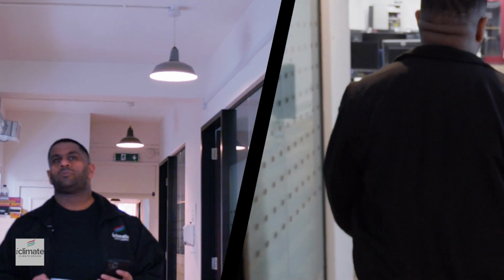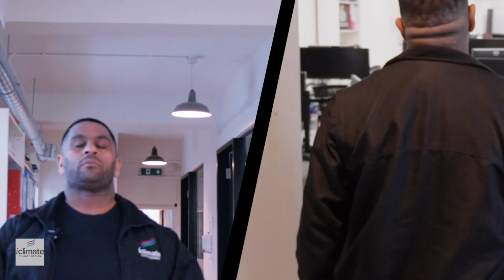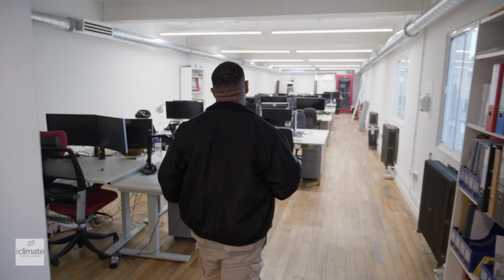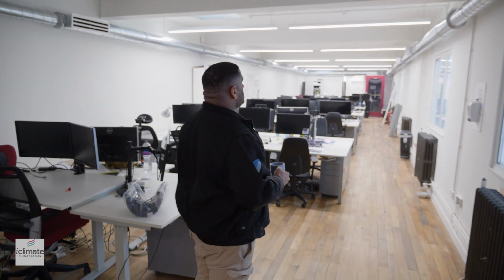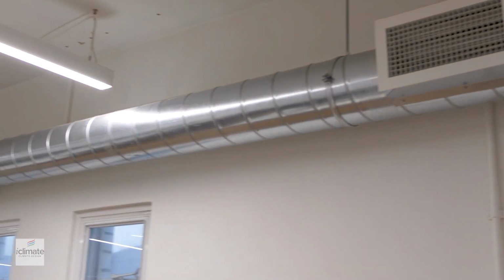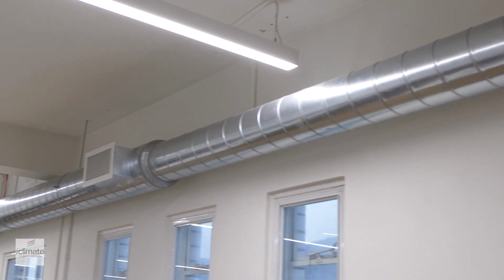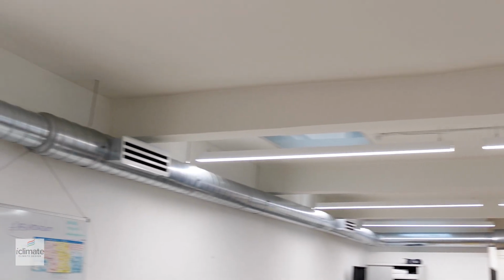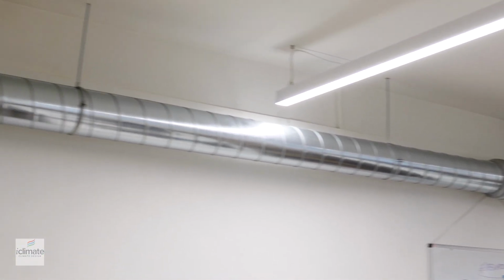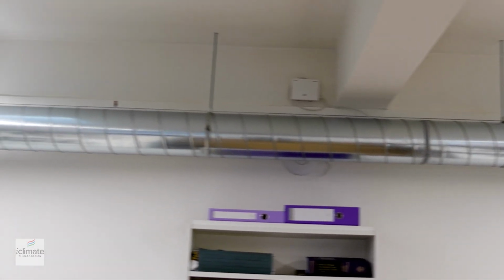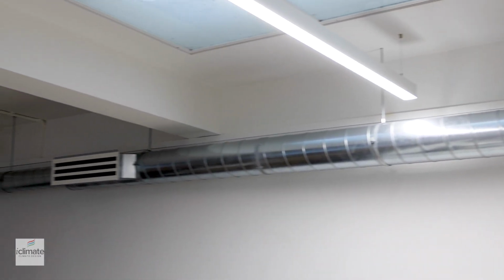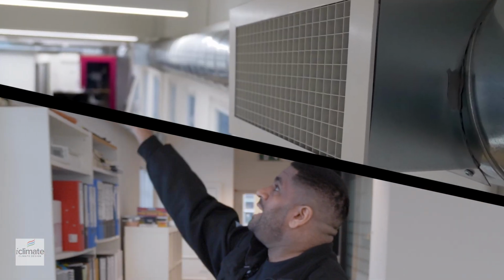Right, so this is the open plan office space. The large silver ducts you can see on the perimeters are the galvanized steel ductwork which carries the warm air out of here and brings in fresh air into here. It's spiral ductwork. We've kept the ductwork as high as possible, you'll see. We've used it on the perimeters of the ceilings, so we don't interfere with the existing lighting detail or anything else that's going on in the ceiling. It's a retrofit project. So these above me is the extract side.